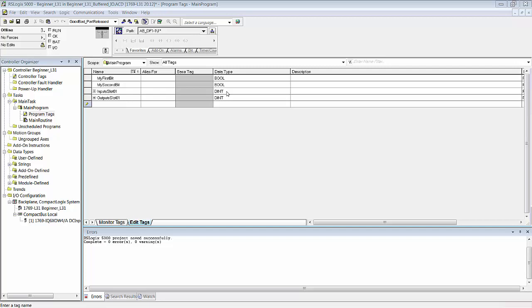Plus, if you decided you wanted to produce or consume any of these tags—that's a very advanced subject, but basically it means you can set up a tag as being produced from a processor out onto the backplane through a bridge card out onto some network anywhere in the whole world, and then somewhere out there you're setting up a processor to consume it. Regardless of whether it's a Boolean, single integer, or integer, when you go to produce it it's going to be changed to a dint. So it actually runs a little slower producing a Boolean than it does producing a dint over the backplane out onto the network.